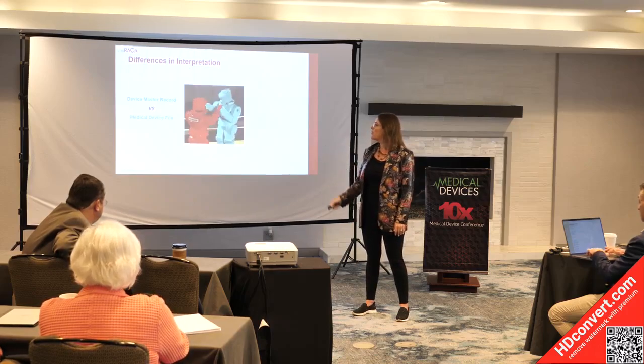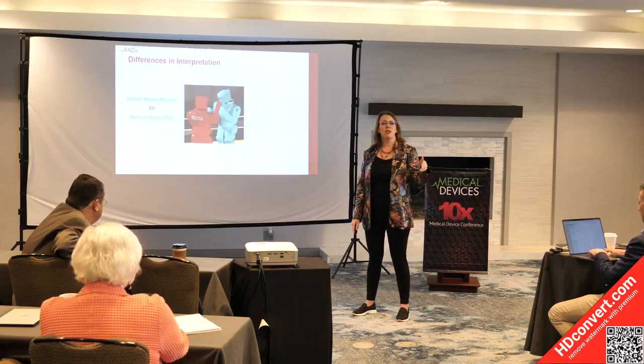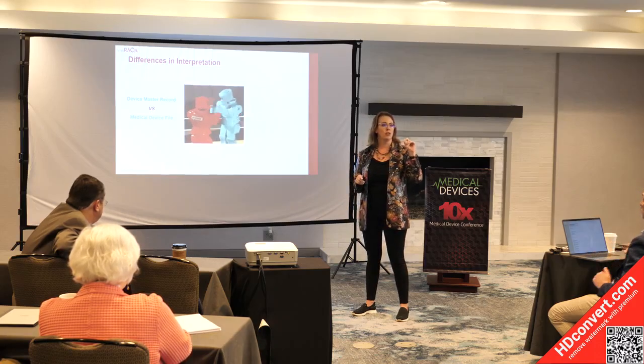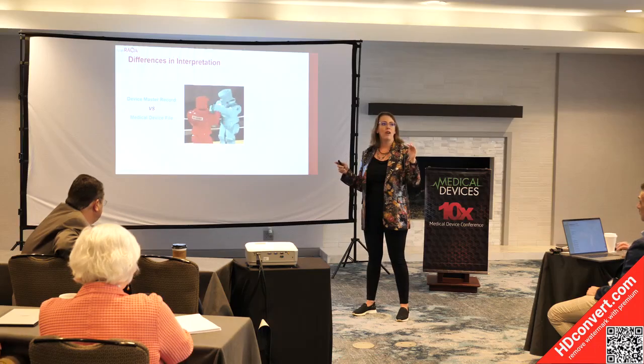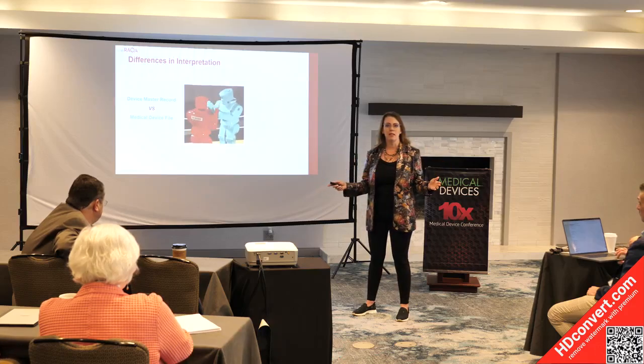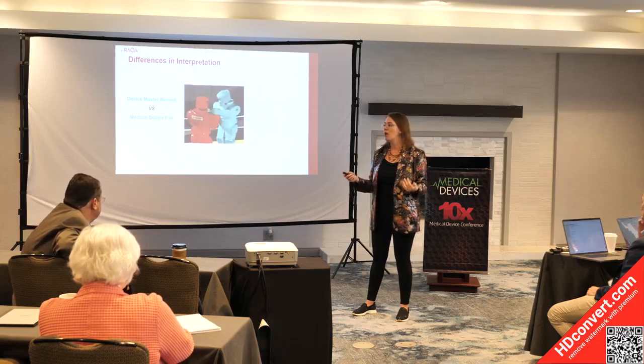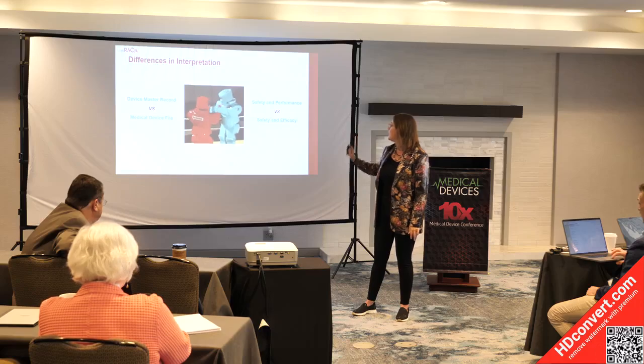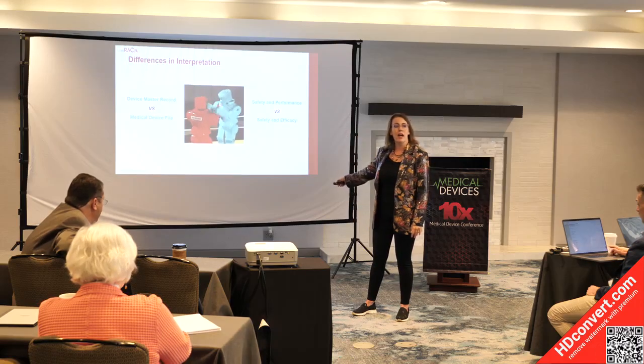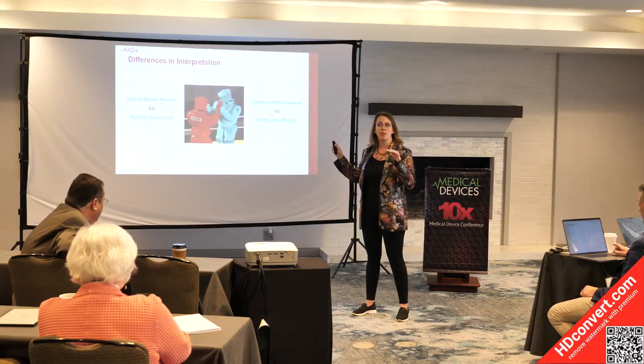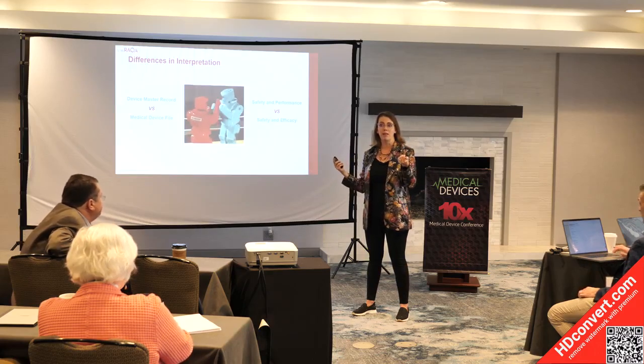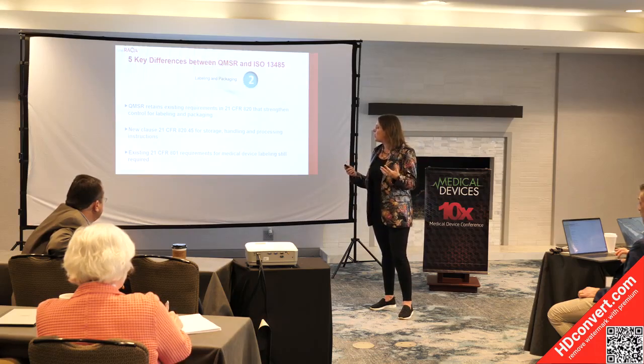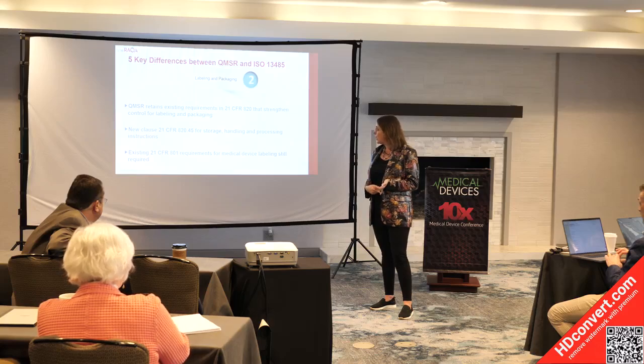The term 'Device Master Record' is replaced with 'Medical Device File.' On its surface that doesn't seem like a big deal — it literally just adds the intended use to what used to be the Device Master Record. However, per the practical guide, it also includes a whole litany of other materials not normally part of a DMR. It also changes the terms from 'safety and efficacy' to 'safety and performance,' which per the FD&C Act — and per Merriam-Webster — are two very different concepts.